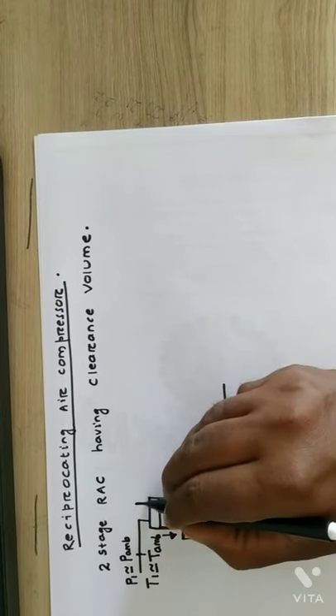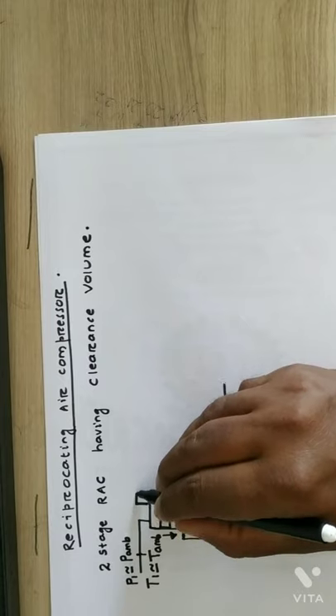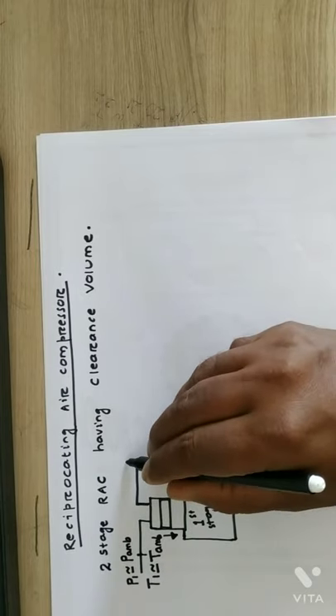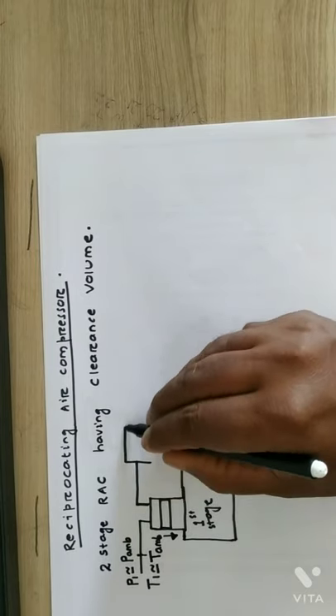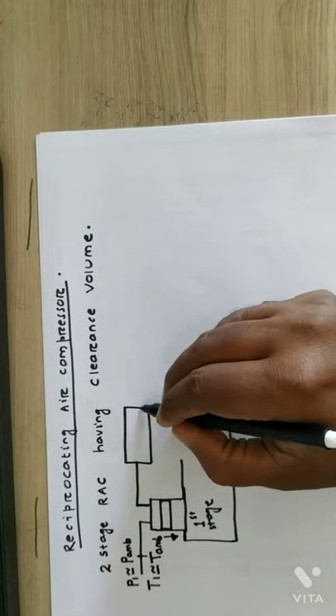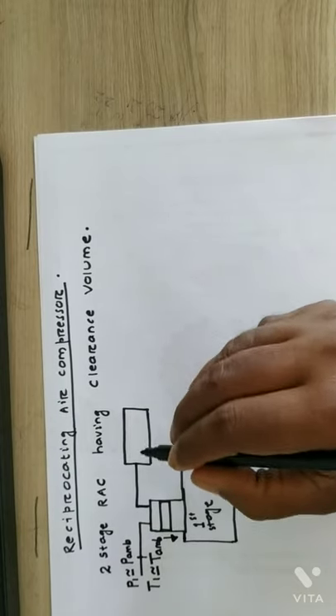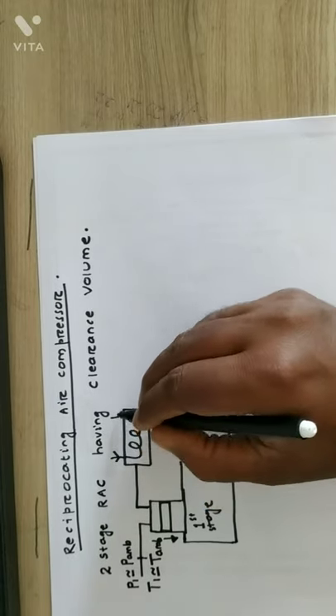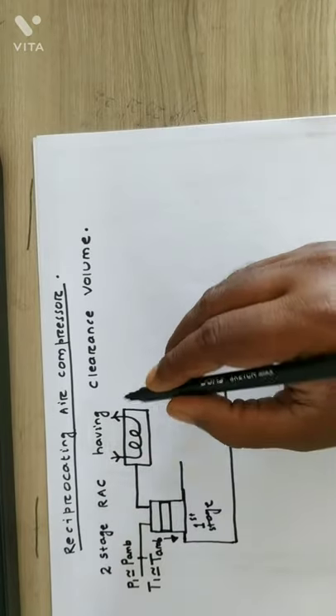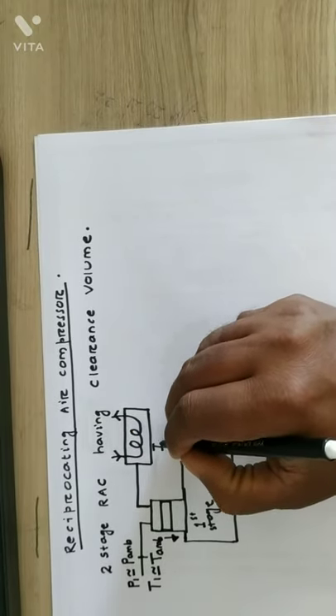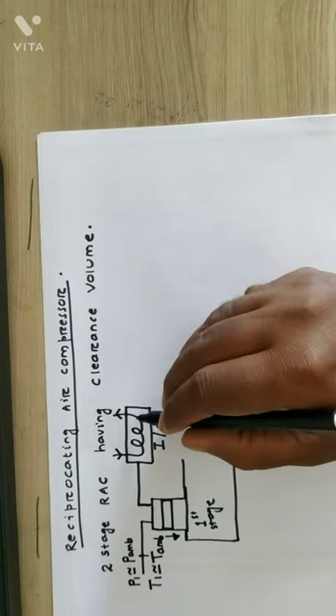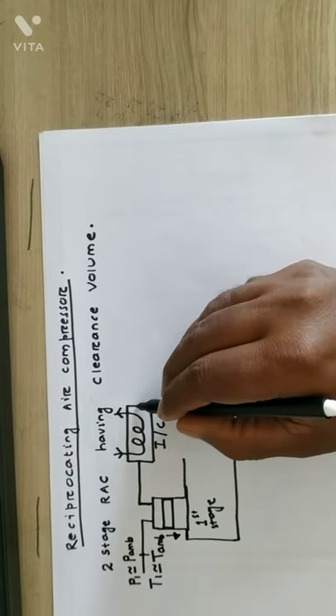The high pressure air will be delivered into the second stage compressor. Before being delivered to the second stage compressor, there is an intercooler arrangement. There will be cooling water circulation — cooling water in and cooling water out. This is called the intercooler, and it is necessarily a constant pressure heat exchanger.